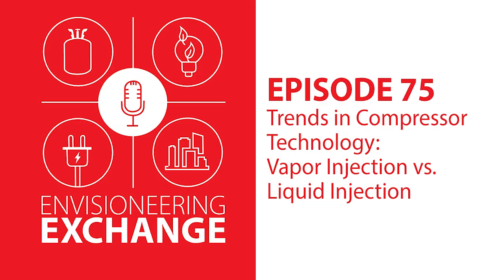And then you've mentioned both vapor and liquid injection technologies. Can you talk about how both of those work and what's the difference between them? So on the first question, as you said, it's not an off-the-shelf compressor. If you look at your standard scroll compressor, you have a discharge port and a suction port. But if you look at a compressor with injection, now you have a third port, which is your injection inlet essentially.